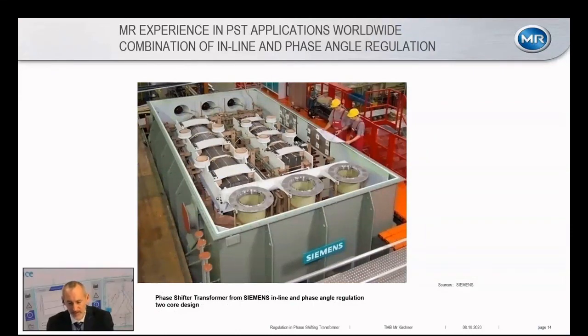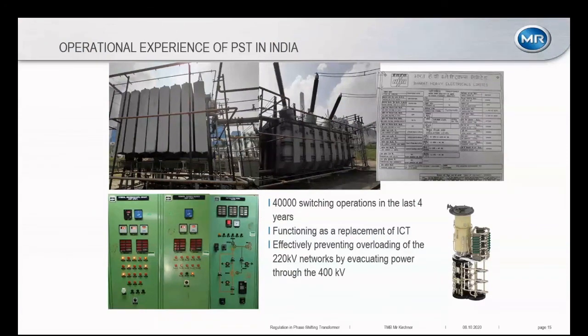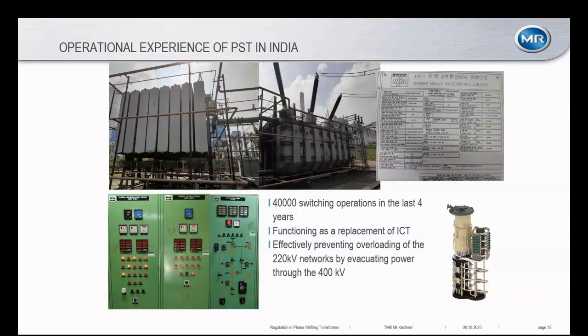Another example is a small unit with two active parts and three OLTCs manufactured by Siemens. Finally, one unit installed locally — you can see the bypass switch in the picture with the green cubicle. We heard at the beginning that it had about 40,000 operations over four years — moderate for a PST OLTC, as we typically see up to 20,000 operations per year. In general, OLTCs in PSTs see far more operations compared to normal power transformers.